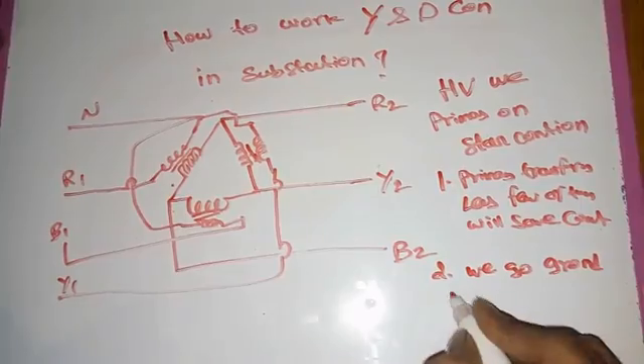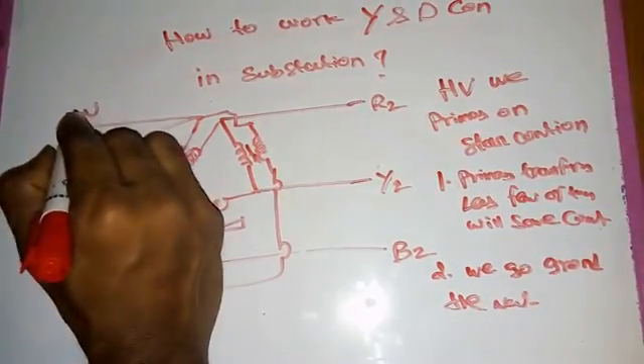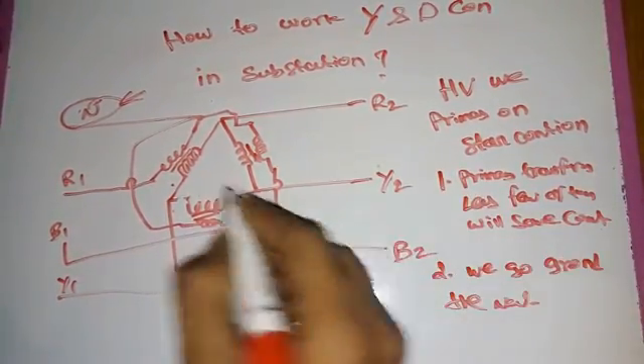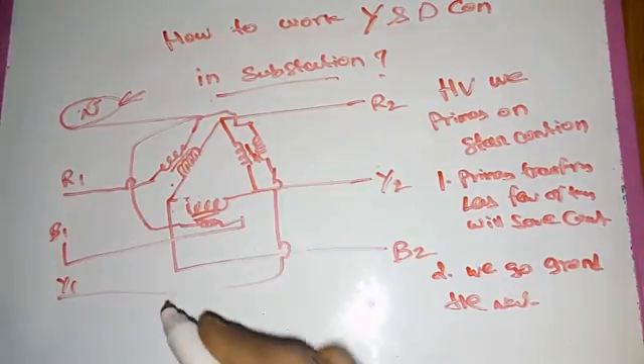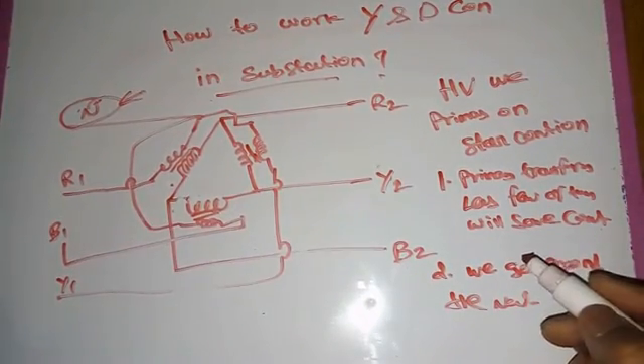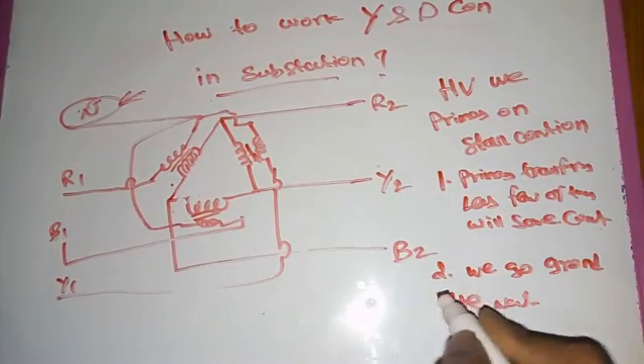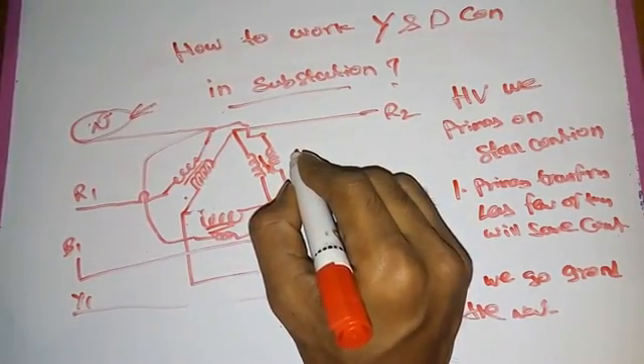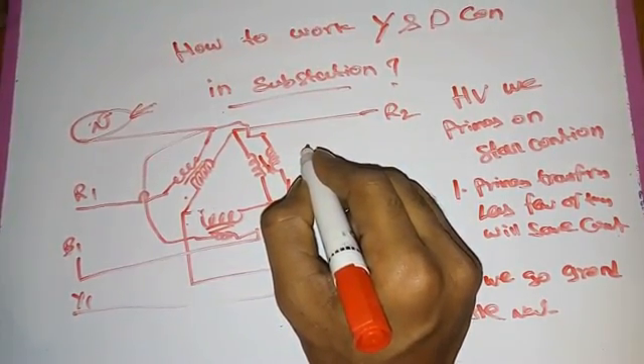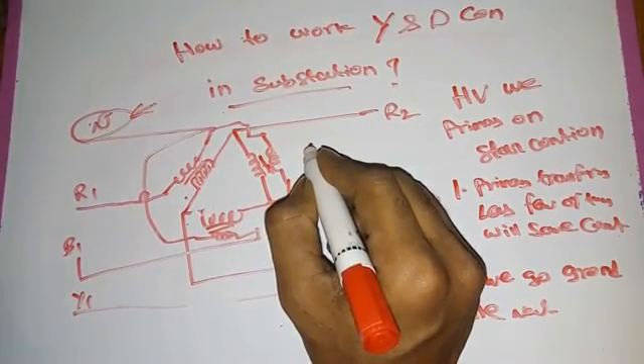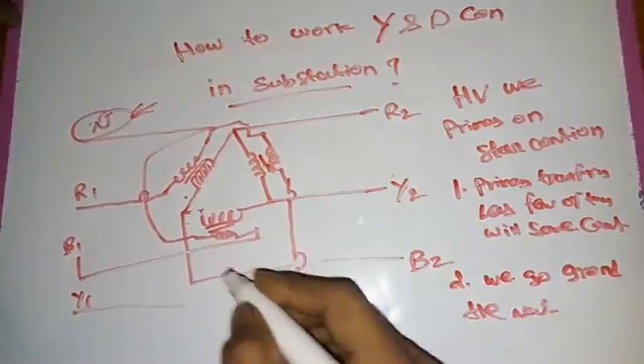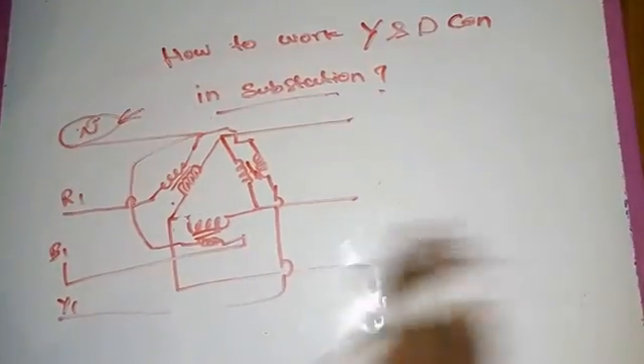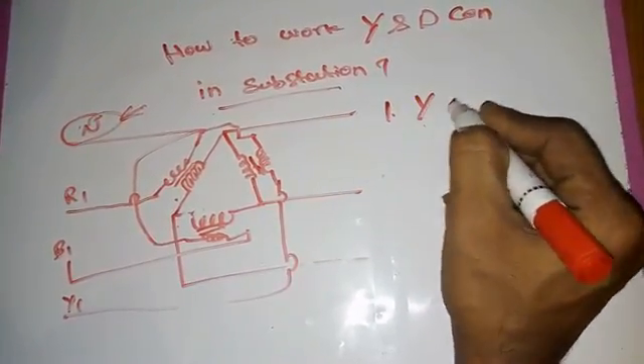The second point is that the neutral is also available in the primary star connection, and we ground this neutral. In HV transmission substations using star-delta, a large number of unbalanced currents also remain stable. Additionally, the star-delta connection has no third harmonic issue on the primary side.